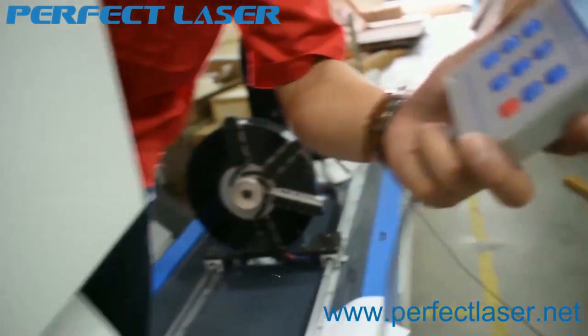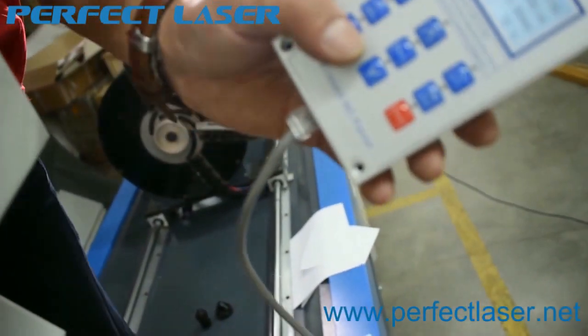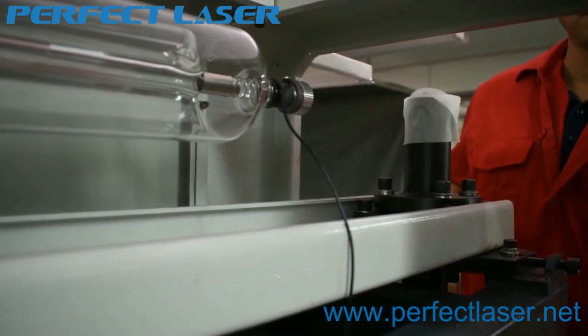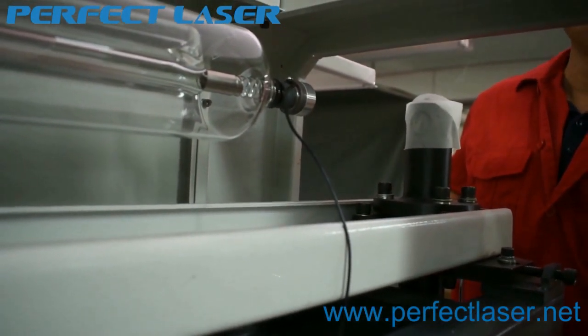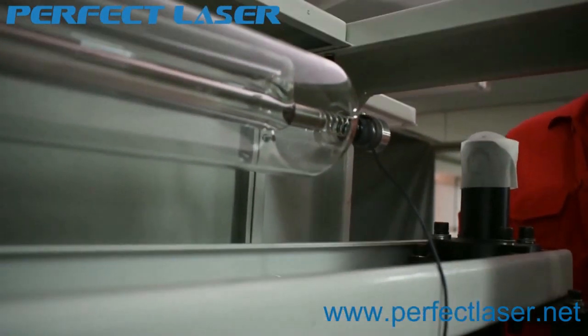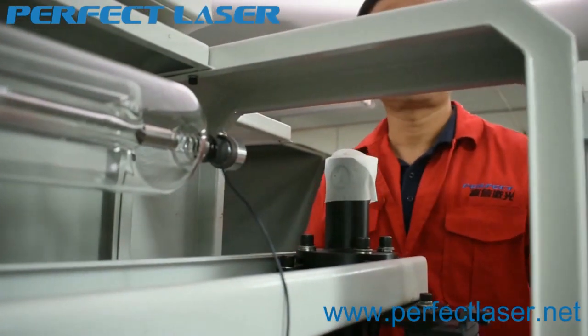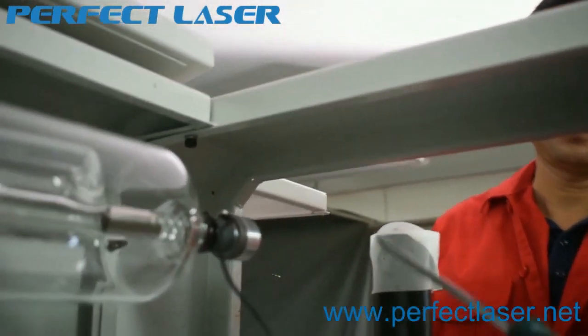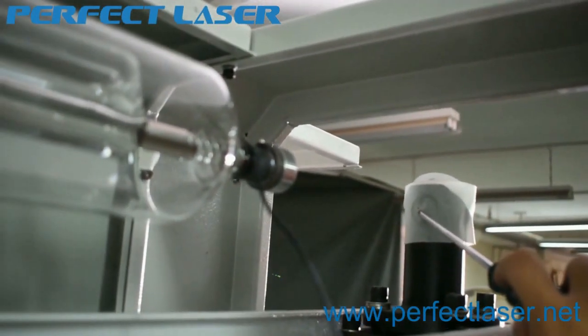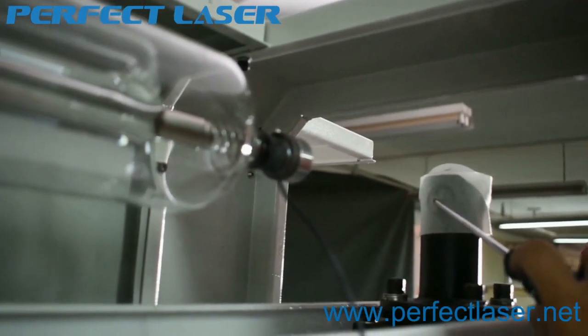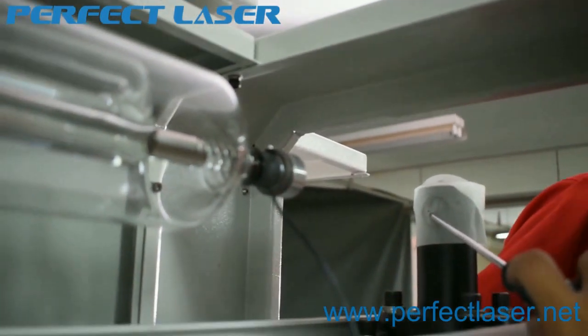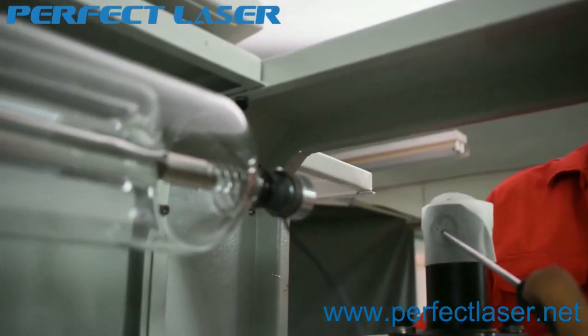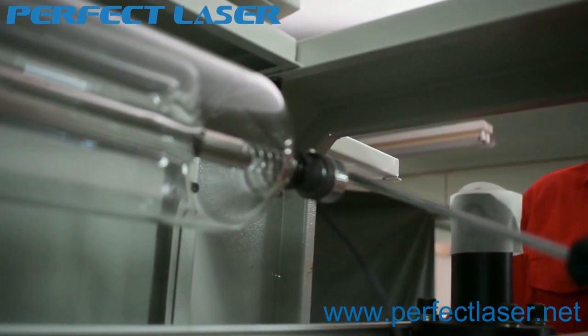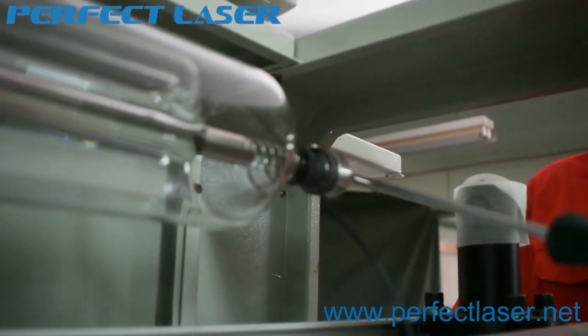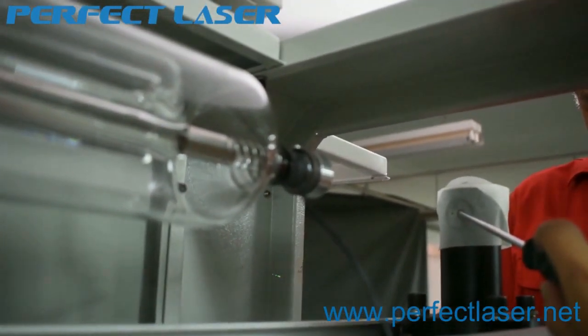We use the DSP panel and press the manual laser, the first one. Press once, and the laser beam will come out once. And then you will see there is a hole in the circle, but now the hole is in the left side of the circle. So that means it is not in the center of the hole. So we have to align the laser beam to make sure that when the laser beam comes out, it will come out in the center of this hole.